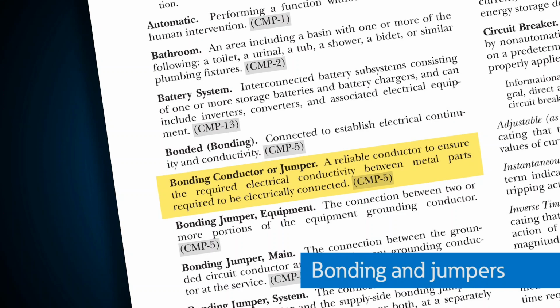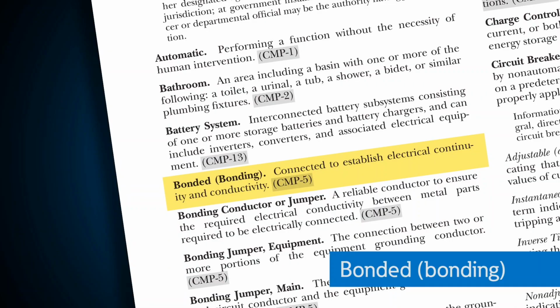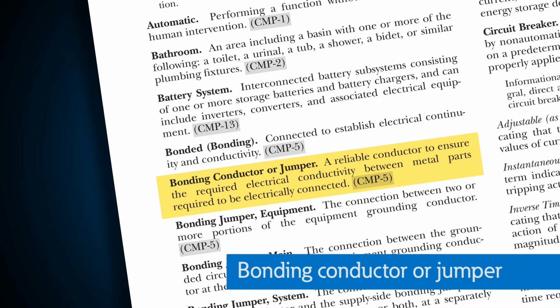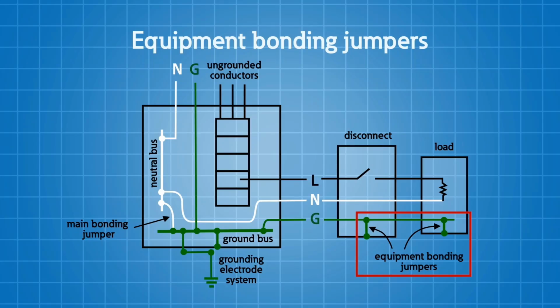Now, bonding and jumpers. So we're going to get into an area where we're pulling things together now. We're talking about bonding, and the National Electrical Code defines bonded as connected to establish electrical continuity and conductivity. This is a very important term as we work throughout the power distribution system. Bonding conductors, or what we call jumpers, are your reliable conductors to ensure the required electrical conductivity between metal parts required to be electrically connected together.